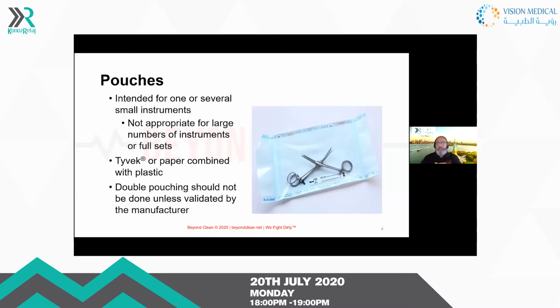And as you can see in this picture, some of our surveyors say if your instruments are not open like this, they could be considered contaminated. So this is a point of contention here in the United States as we work with our surveyors, because many manufacturers will tell you that as long as they are not ratcheted or closed or locked, the sterilant can come into contact with all portions of the instrument. So very important, just in case a Joint Commission surveyor might mention this to you.